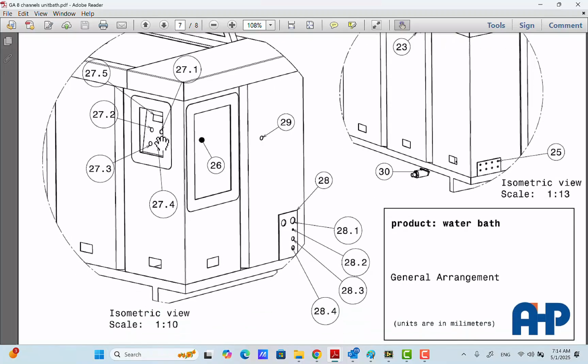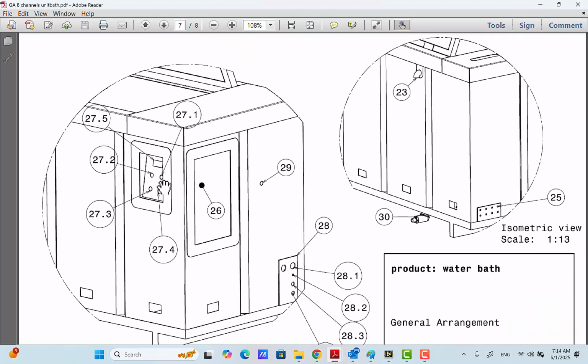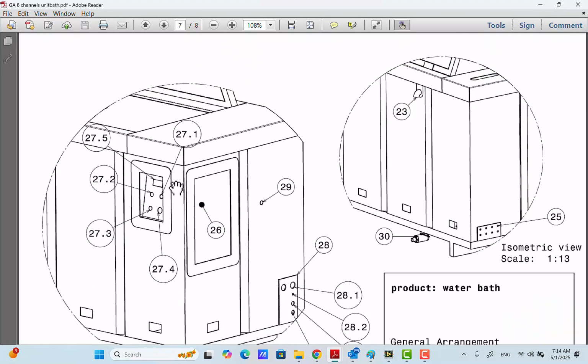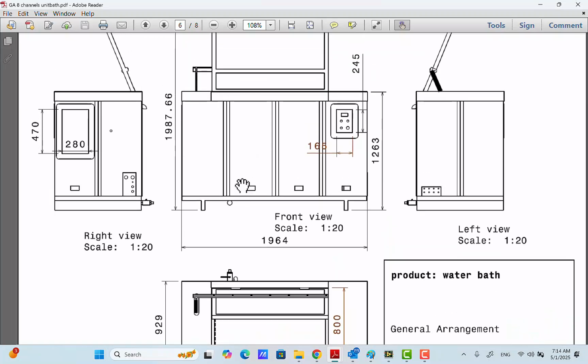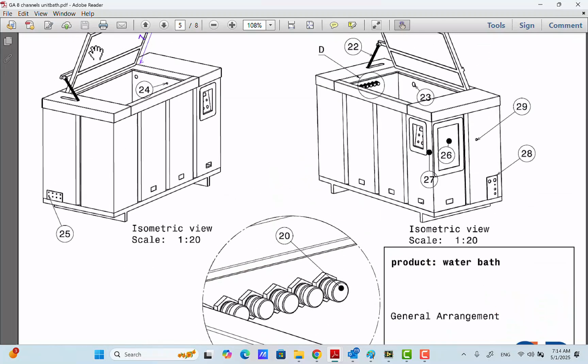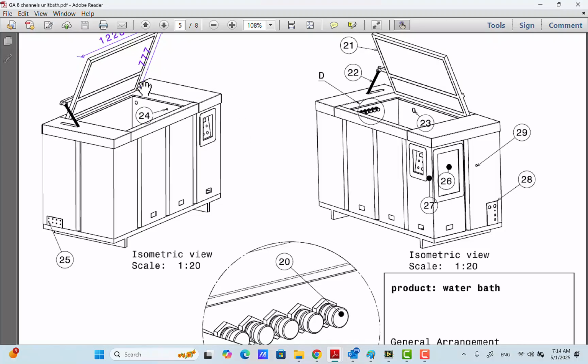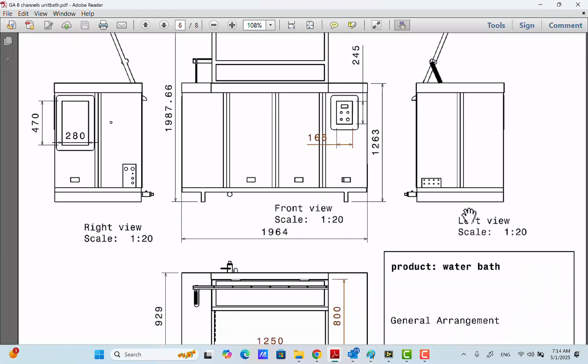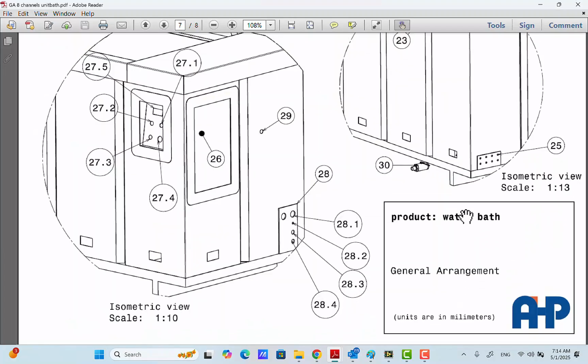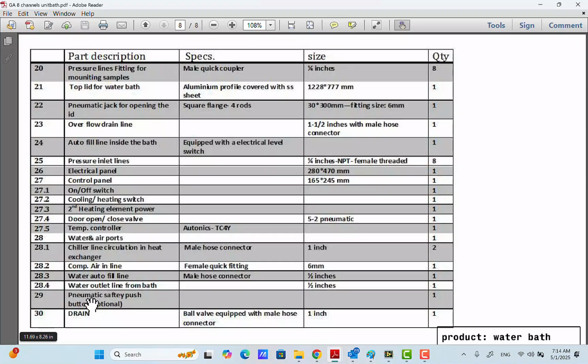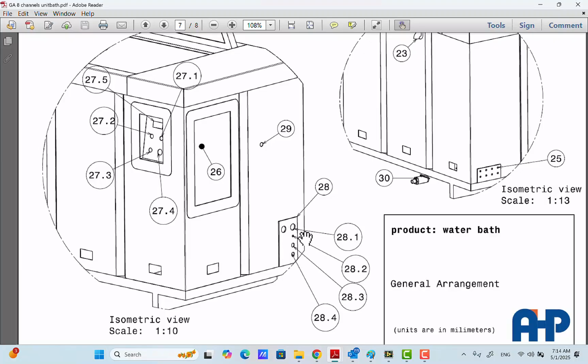You have a key for opening of the door. This key is not an electrical key. I mean, when you receive the machine and you want to open the lid without any electrical connection to the tank, the only thing needed is to connect the air line here. Compressed air line is 28.2.